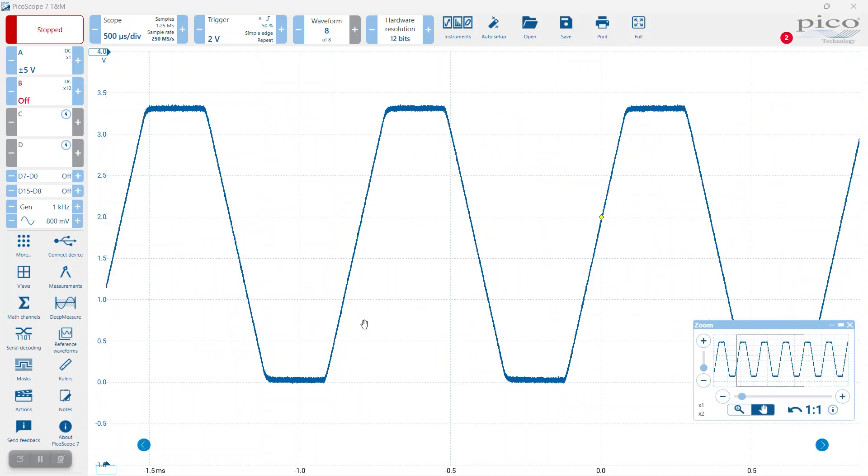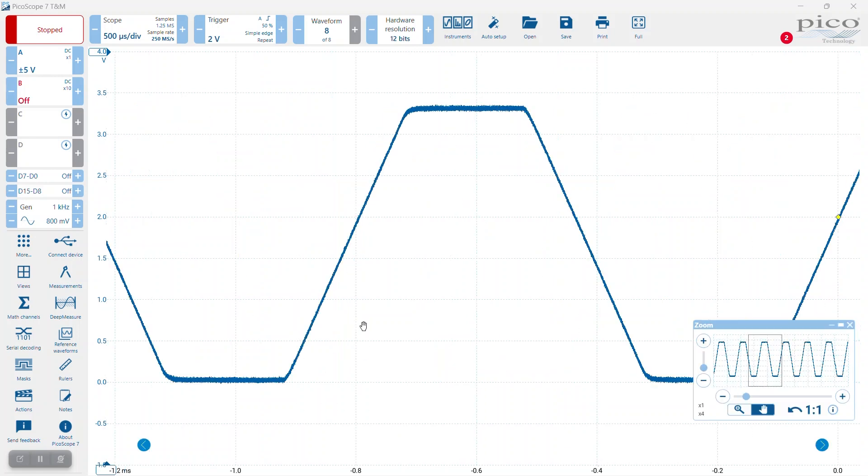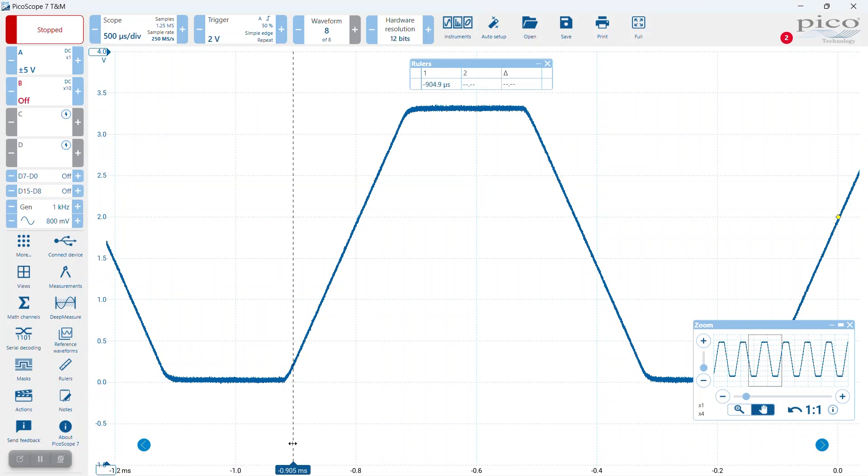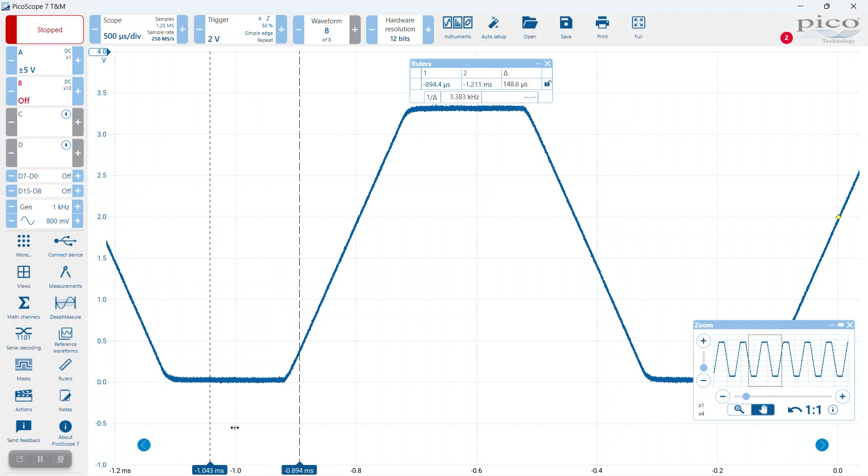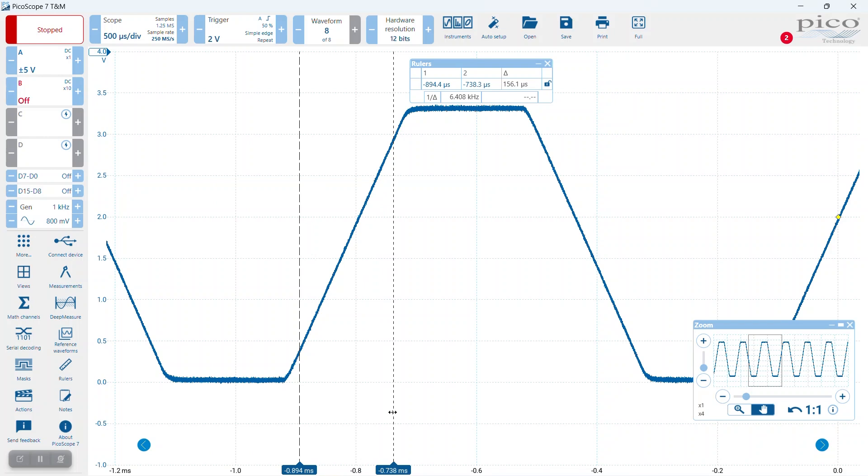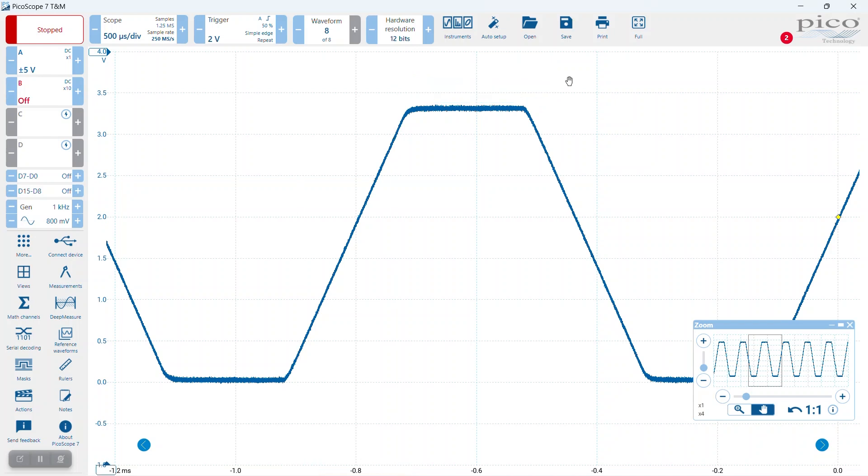If we expand that waveform a little bit and use the rulers, we can see that the rise and fall time is in the order of 155 to 160 microseconds - that is representative of a good waveform.